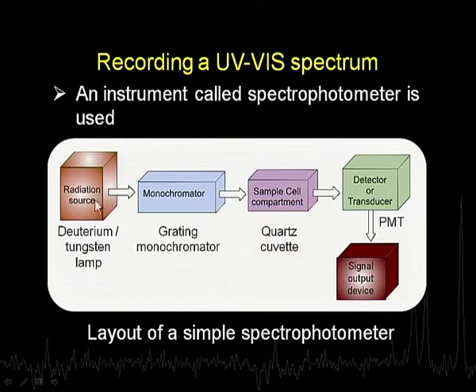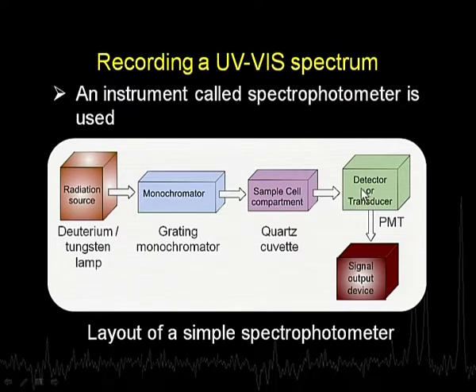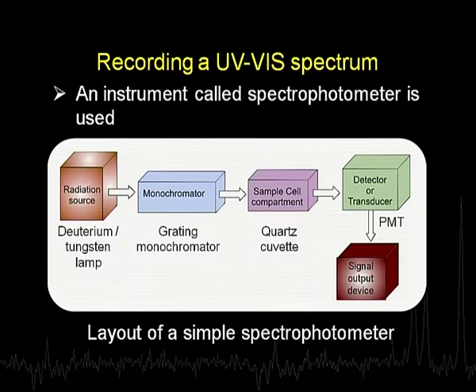The monochromator can be tuned to give say 200, 201, 202 nanometers or whatever wavelength we want. So from the source, polychromatic radiation passes through the monochromator and we get monochromatic radiation that falls on the sample in a cuvette - typically a quartz cuvette. If the sample has some absorbing chromophore, some of the radiation will be absorbed, and whatever comes out is detected by the detector, which is typically a PMT, a photomultiplier tube. This detected signal is then sent to an output device which gives out a spectral output. There are five essential components which are a must for any spectrophotometer.